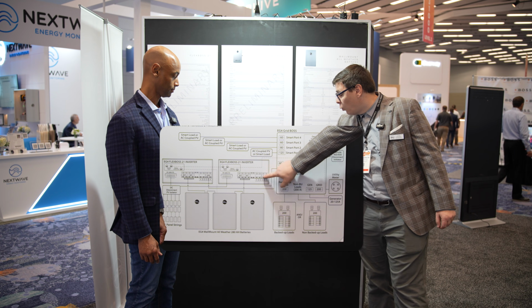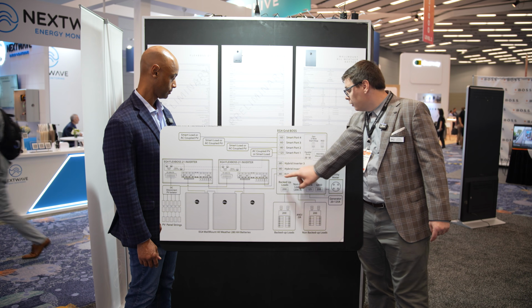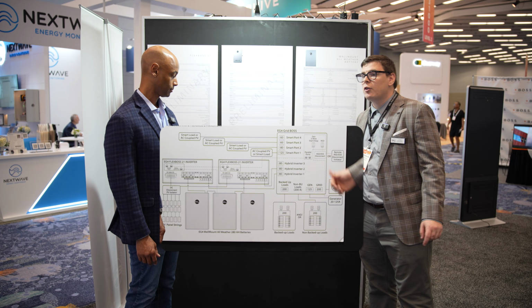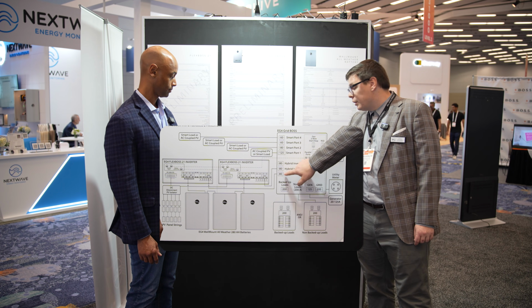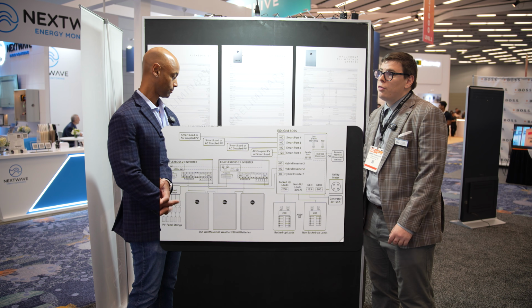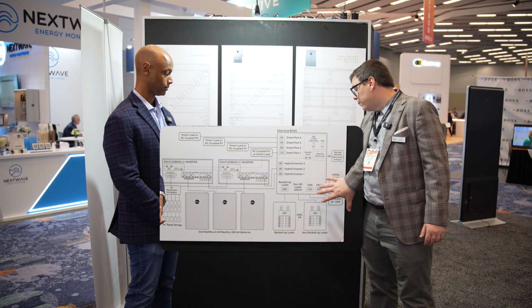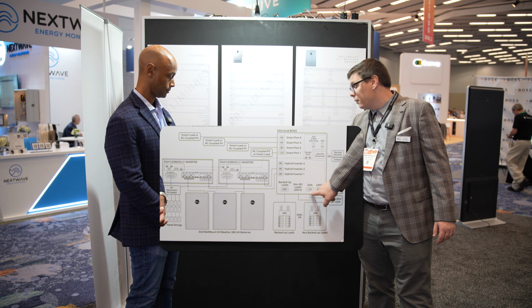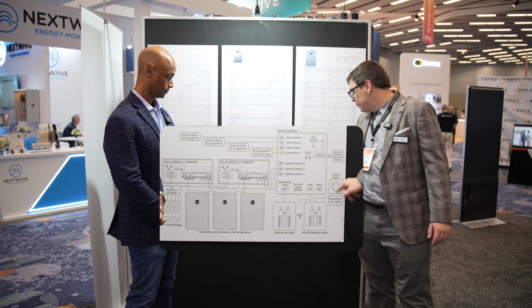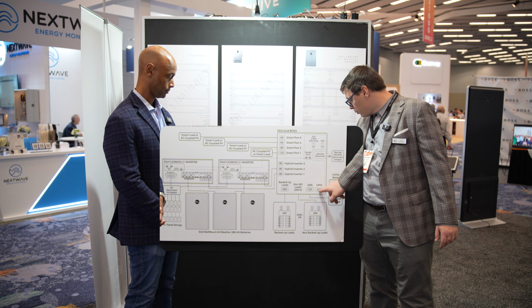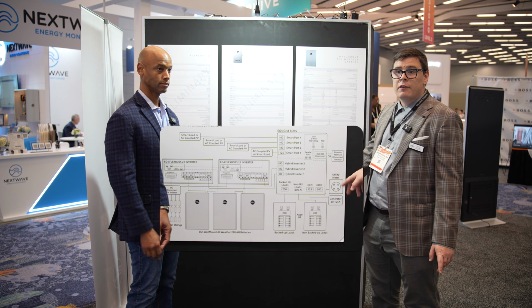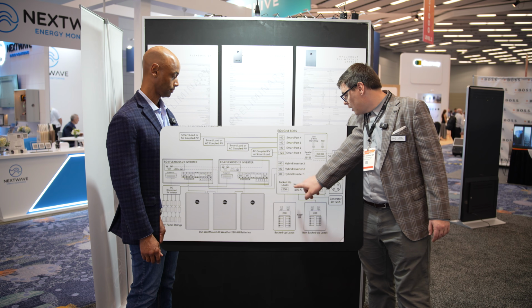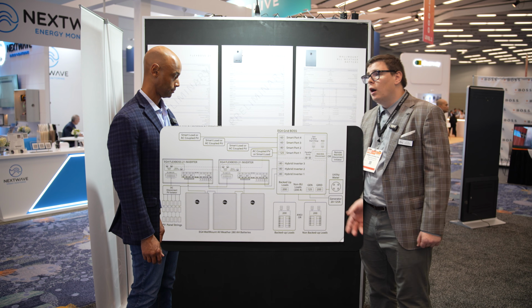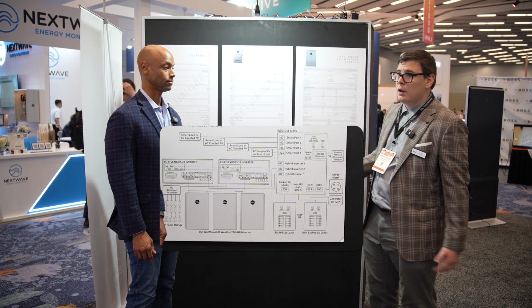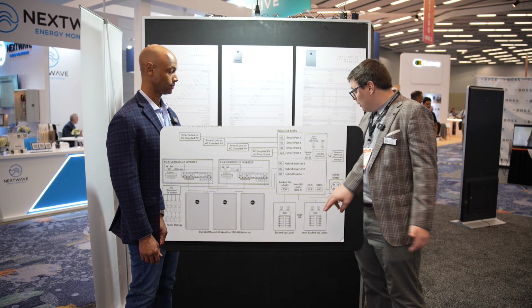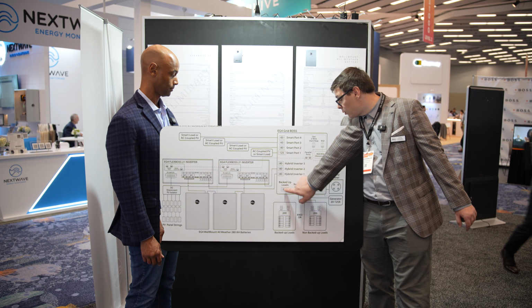The 3 inverters, as you can see, I've got one line, just one conductor per inverter. It goes to an 80 amp circuit. It's obviously running about 70 amps continuous, and you can tap in up to 3. So people could do a house with 60 kilowatts of solar with the GridBoss. The generator down here has a 125 amp dedicated load breaker. The utility meter goes into the grid breaker, which is an Eaton 10 kA 200 amp switch. We have a 200 amp bypass for a non-backed up load panel. So some homes have 2 load panels and people are okay with one not being backed up. Of course, you can always parallel those load panels, but you can have one that's not backed up, and then of course the house comes out of here.